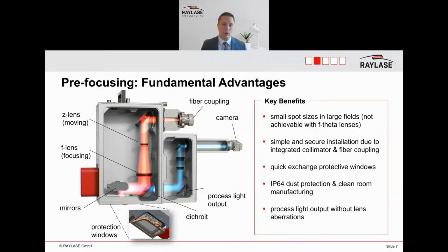Moreover, you have a quick exchange protective window at the bottom. Basically you have two windows. You have an inner protection window, which seals the housing permanently, and this cannot easily be removed by a customer. And then you have an outer protection window, and this is just a clip-on system, so you can remove it and replace it within a matter of seconds, so your production is not stopped.